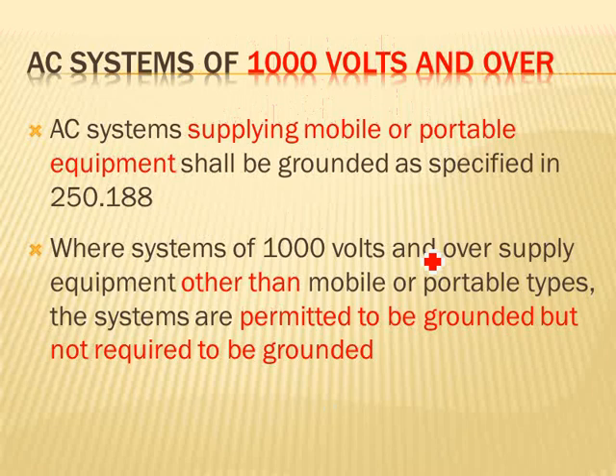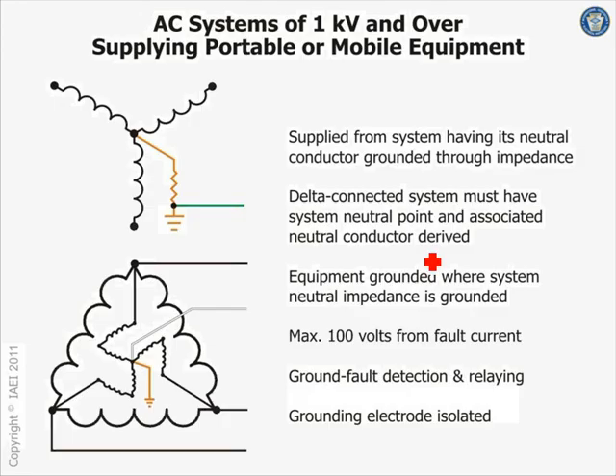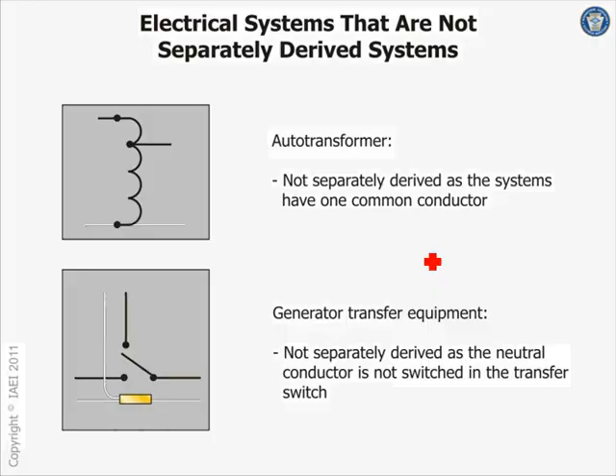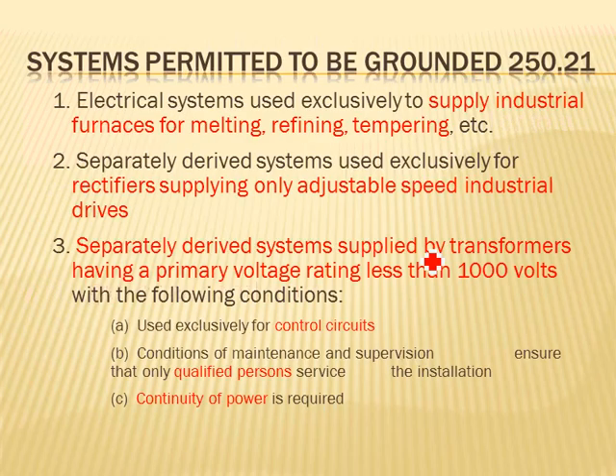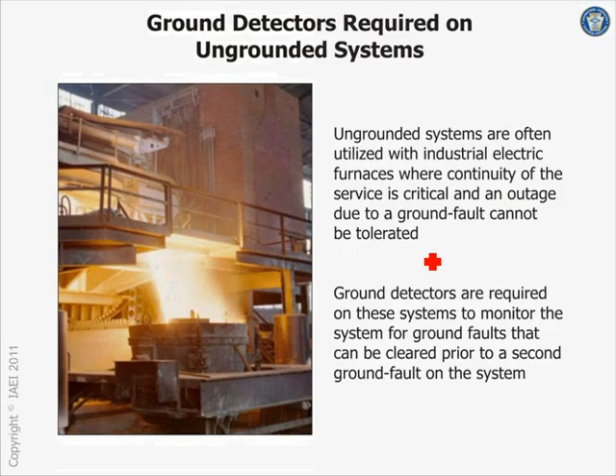So now over 1,000 volts. If you're over 1,000 volts, it's optional to ground. But I'm sorry, these are must ground: if you're using portable or mobile equipment, you must ground your system. You can ground it through an impedance or solidly ground it. But you have to ground it if it's feeding this equipment. So with your system, let me go into the ungrounded system. Okay, systems permitted to be ungrounded. This is really interesting. The ones that are permitted to be ungrounded. This is where your transformer supply has primary voltage, exclusively a control circuit, with a condition of a qualified person. That's where it gets you the control circuit ungrounded. Let's go back into here.